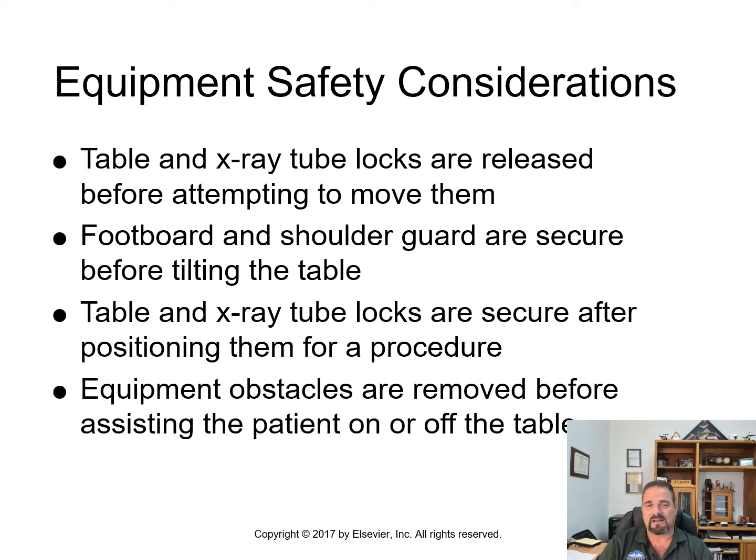Also, watch for any equipment obstacles. One of the most common things that I keep seeing in the hospital where I work, and also in the urgent care center, is that step stool. Do not slide that step stool, which helps people up onto the table, underneath the table. Because remember, the table can go up or down and it will break the motor or damage the table in some way. Just make sure all the obstacles are clear from the unit or from the table before you move the patient around.